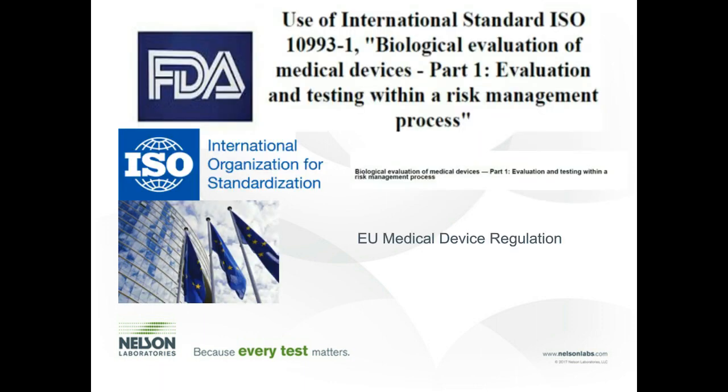But to hit what the recent changes have been, these are the three documents that we have seen and are continuing to see updated for biocompatibility. The first one is the FDA guidance document that was released last year in June. And I really believe that this FDA guidance document is a really well-written and thought-through risk evaluation for medical devices. I would highly recommend, especially if you're considering submitting any results to the FDA, that you really get to know this document, as it does represent the current thought process of the FDA.